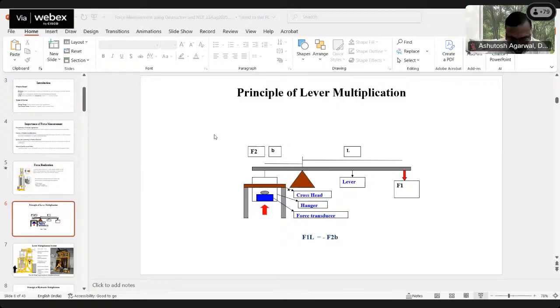Using this machine, one by one, weights can be selected and removed, and the instrument can be calibrated. We call this kind of machine a dead weight force machine. This dead weight force machine is suitable up to about 100 kN, because its height is like a one-story building.